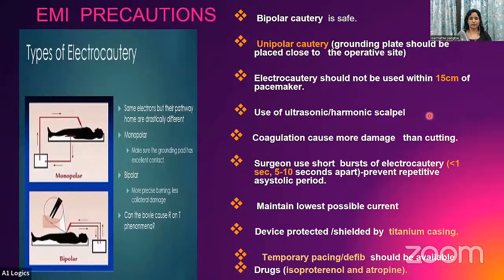that type of instrument. And ask the surgeon to use short bursts of electrocautery, less than 1 second, 5 to 10 seconds apart, because when you use it briefly, this prevents a repetitive asystolic period. Then the lowest possible current should be used by the surgeon. Recently, many shields made of titanium have also been developed to protect the pacemaker pulse generator. You can also use those, which protect from noise interference and also from electromagnetic interference. And you have to keep the temporary pacing pads and defib pads ready, and also the emergency drugs should be kept ready.